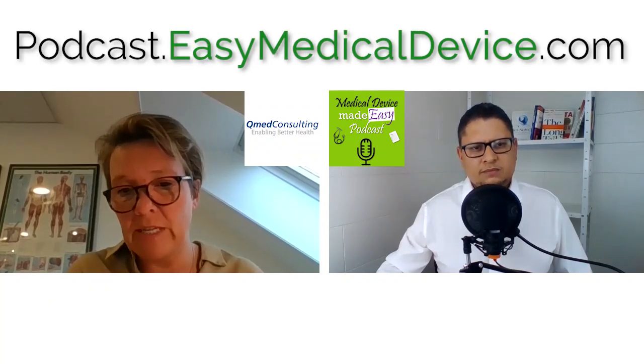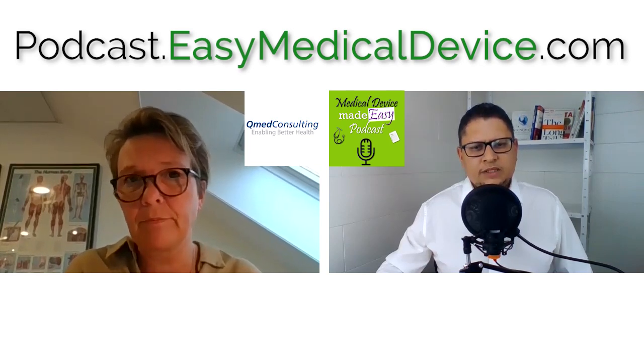Yeah. And of course, a lot of devices would need a clinical investigation. I think it's great advice, for example, when we have a CER under the MDD and we want to go under the MDR, to use this PMCF. Starting to use PMCF now can be really the best strategy for companies because they will use their own product, so there's no need to make any equivalence to anything else. I'm not sure that a lot of companies are starting now. I think they should, but I don't know if the message was spread. They can save some time with notified bodies to really justify their CER. So maybe if somebody's listening, please start your PMCF program now. Yeah.